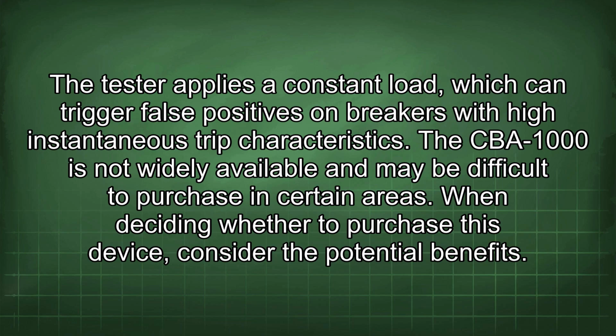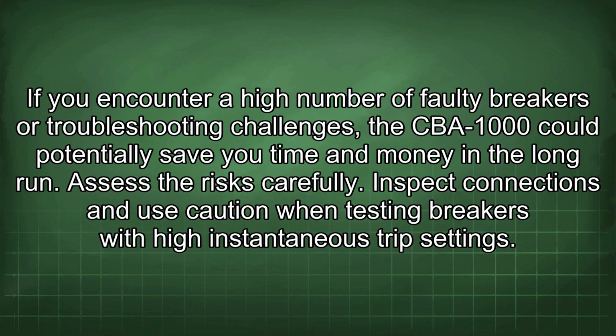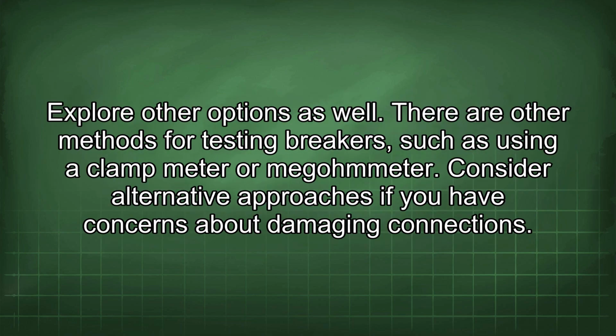When deciding whether to purchase this device, consider the potential benefits. If you encounter a high number of faulty breakers or troubleshooting challenges, the CBA-1000 could potentially save you time and money in the long run. Assess the risks carefully. Inspect connections and use caution when testing breakers with high instantaneous trip settings. Explore other options as well.